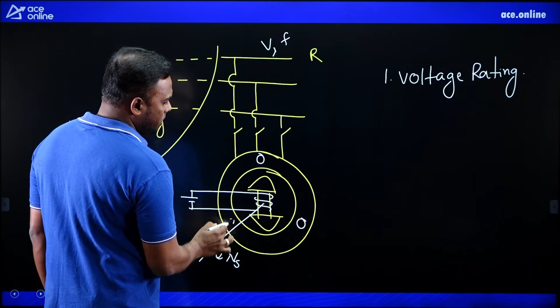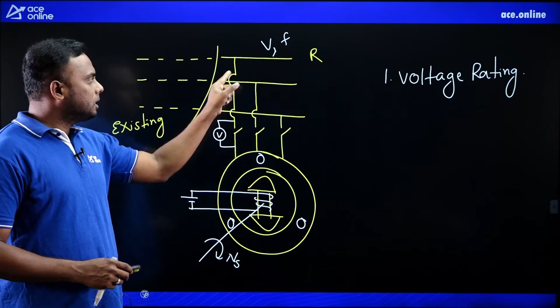How to verify this condition? To verify it, we simply put one voltmeter across the bus bar and the alternator. Now what should be the reading of this voltmeter to say that both are at the same potential? Zero. If the bus bar voltage and alternator voltage ratings are the same, then what is the difference of these two? Zero. So the voltmeter will show 0 reading here. Like that we can easily verify this condition. Suppose the voltmeter is not showing 0; if it shows other than 0, it means the voltages of these two systems are different.